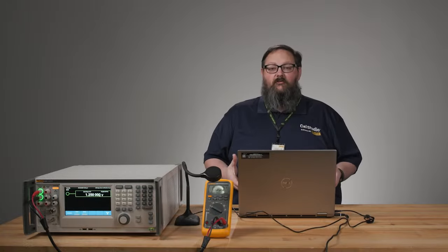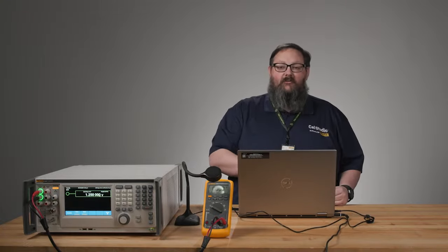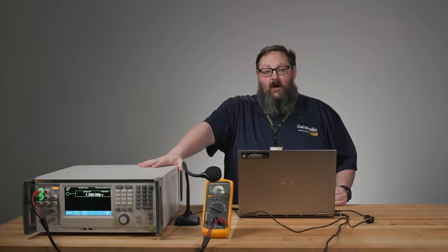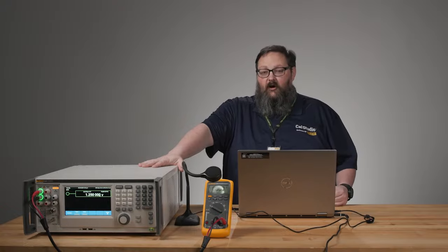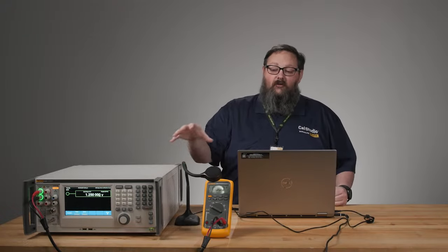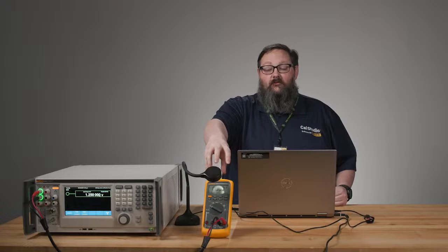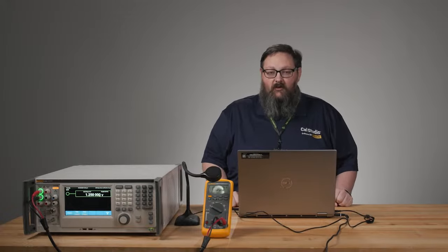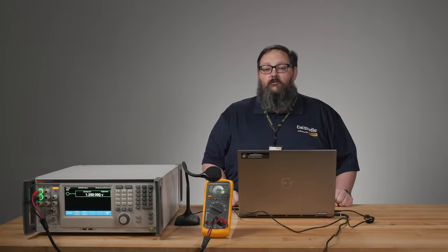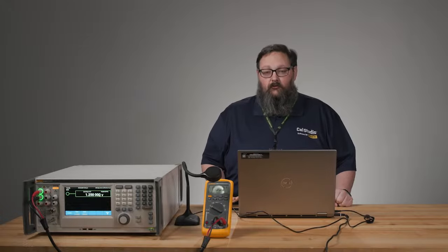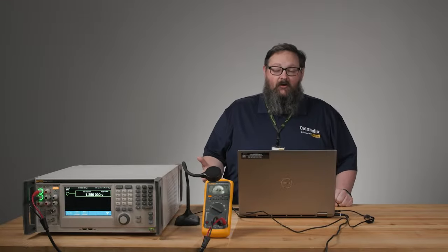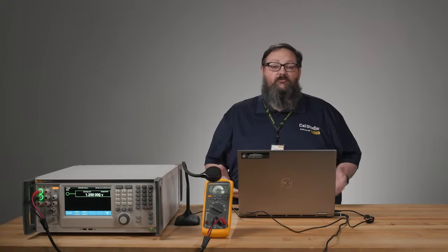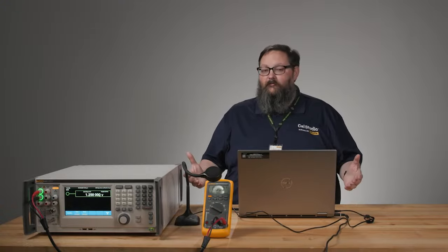And this is an early demonstration where my Optical demo here is going to control my 5560 calibrator through a USB to serial adapter from the browser without any installed software on the computer. And it's going to take readings from the DUT, the device under test, using my webcam. So Optical is a new AI-based image analysis tool that allows us to take readings with both digital and analog displays through really any webcam of sufficient quality. No special camera required, no special positioning or pre-training required. You put your tool in front of it and it just works.